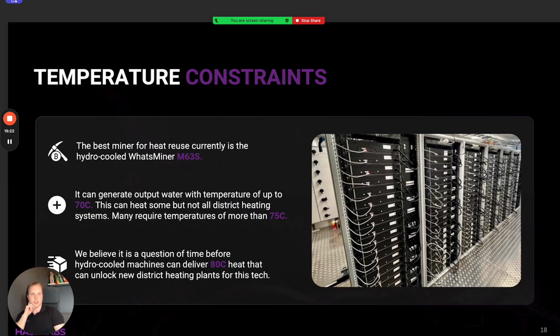Also, for different purposes you need a certain amount of heat at a certain temperature. So the best miner currently for heat reuse is the WhatsMiner M63S, which you can see here from Finland. This machine can generate heat up to 70 degrees Celsius for the district heating system, but most district heating systems need heat at more than 75 degrees. So basically right now this machine can only be used for a certain amount of district heating systems, not all of them.